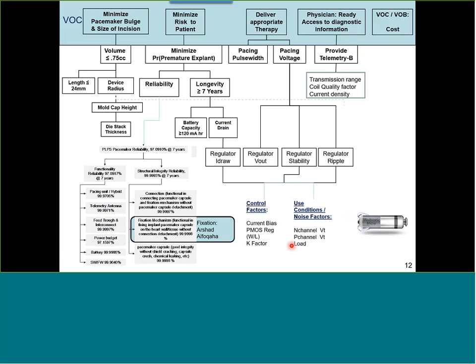We start at the top with the voice of the customer, and we translate it into measurable system requirements. To minimize the size, we have the volume less than 0.75, and that drives down to a length and radius requirement. Minimize the probability of explanting it prematurely, and that drives down reliability requirements. This is the real reliability flow down for Micra, at the time called PLPS, percutaneous leadless pacemaker system. And then requirements on the pacing voltage and the requirements of access to diagnostic information for the physician.